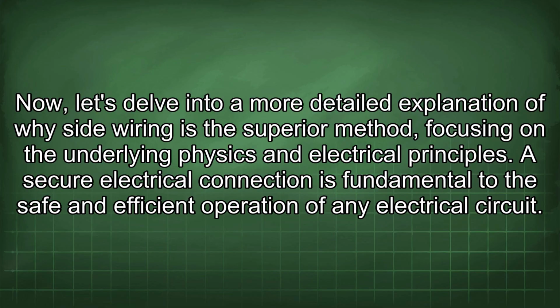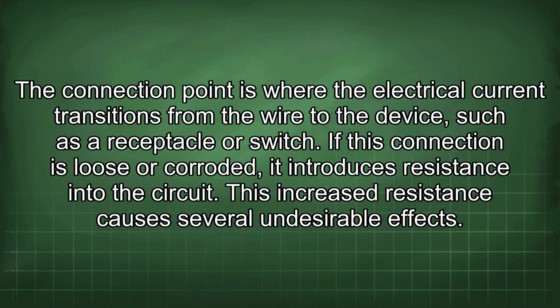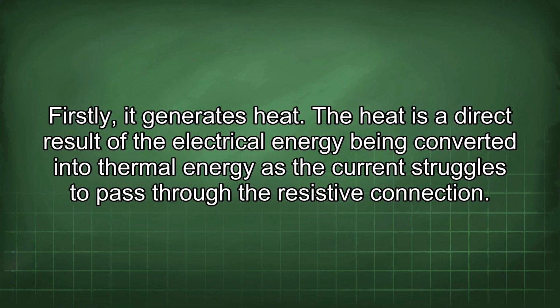the underlying physics and electrical principles. A secure electrical connection is fundamental to the safe and efficient operation of any electrical circuit. The connection point is where the electrical current transitions from the wire to the device, such as a receptacle or switch. If this connection is loose or corroded, it introduces resistance into the circuit. This increased resistance causes several undesirable effects. Firstly, it generates heat. The heat is a direct result of the electrical energy being converted into thermal energy as the current struggles to pass through the resistive connection.